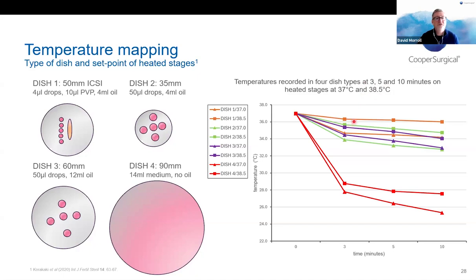So in this case, it's an ICSI dish that's on a heated stage at 38.5 and it's relatively well controlled, but it will decrease over time. So this decision to go to 38.5 is protective, but that decision to use 38.5 is something you need to test and validate in your own system, depending on what sort of dishes and volumes of dishes you use.